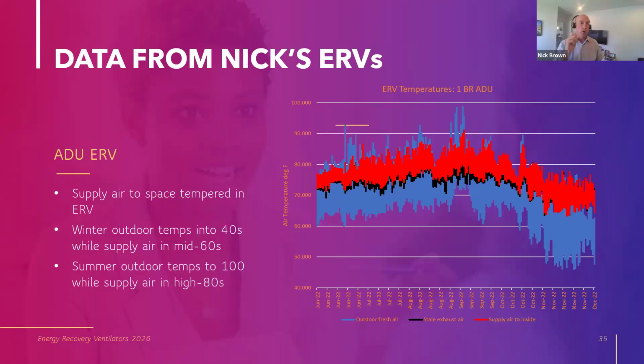Here's the temperatures. I put a HOBO logger on all 4 air streams, and here's what it showed me. This is a period from June to December. The blue is the outdoor fresh air temperature, and you can see that varying here in Long Beach from about 46 degrees on the coldest November day, and we almost broke 100 in August and September of 2022. The red bars are the temperature of the supply air coming into the unit. So you can see visually that the range of supply air temperatures, the amplitude, is dampened. It's cut like in half, right? By the heat recovery function.